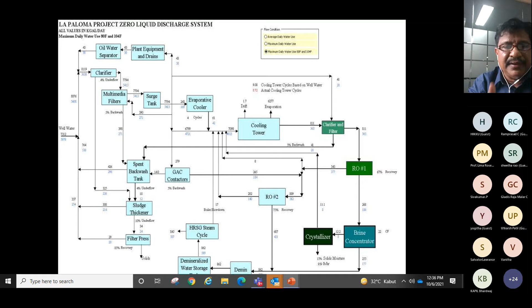So that is called the cycles of concentration. The cycles of concentration is nothing but the TDS in the cooling water divided by TDS in the makeup water. Normally the cycles are in the range of 4 to 6 COC. So our objective is to increase the cycles of concentration, thereby you reduce the makeup. So this is one methodology we employ in total water management.